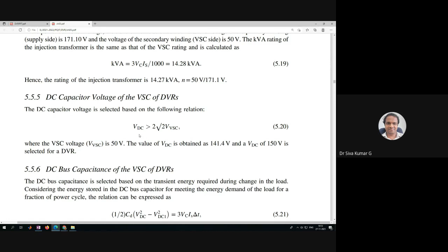Coming back to the DC bus capacitors, the capacitance which we require is such that if any disturbance occurs on the AC side, the rate of change of energy has to be withstood here. That is, half CDC VDC square minus half CDC VDC1 square is equal to 3 times the voltage converter rating times the rated current times delta T. Delta T is the time in which the rate of change of energy will occur.